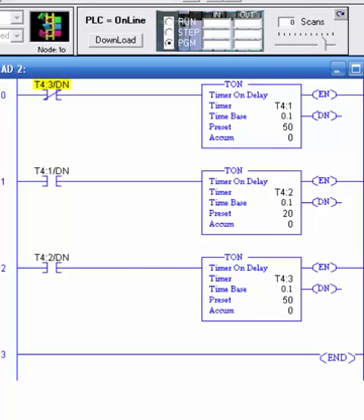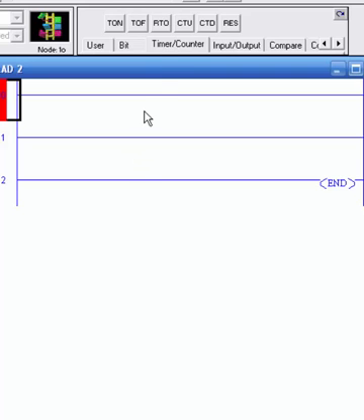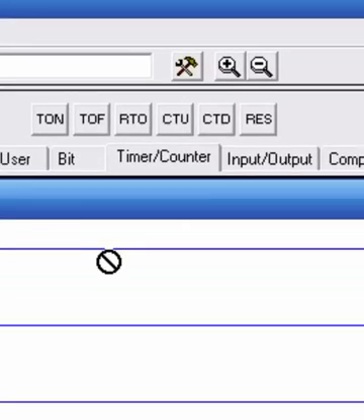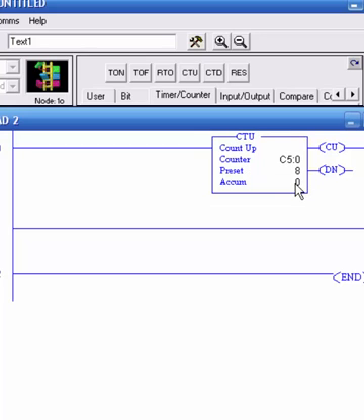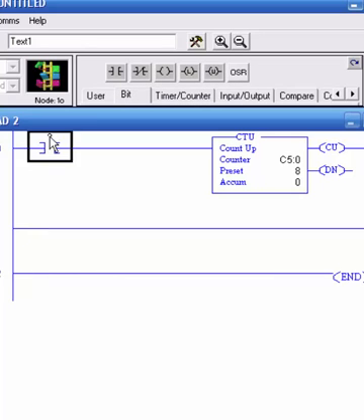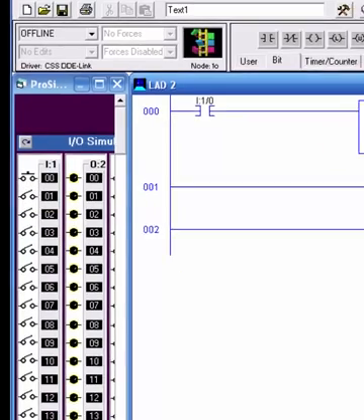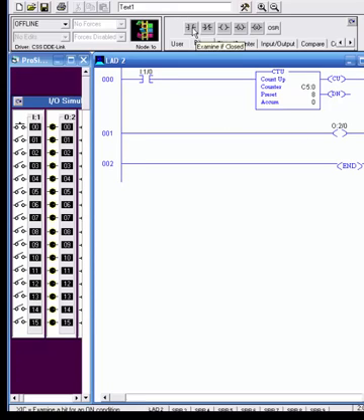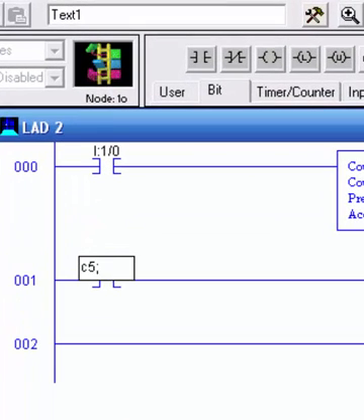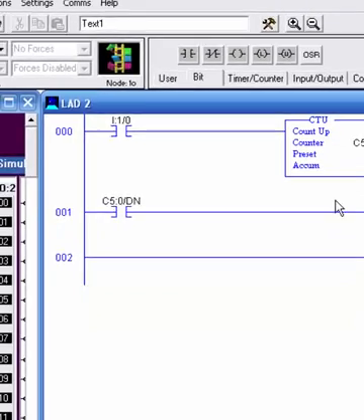The last topic before we work with timers and counters is counters. Let's grab a CTU (counter up) - these are going to be C5s. The preset value - let's put 8 in there. When this counts up to 8, it'll be done. To count, I'll grab a bit and make this a pushbutton: input I:1/0. Every time I push this it will count up. I can monitor the done bit with an OTE at O:2/0, referencing C5:0/DN.